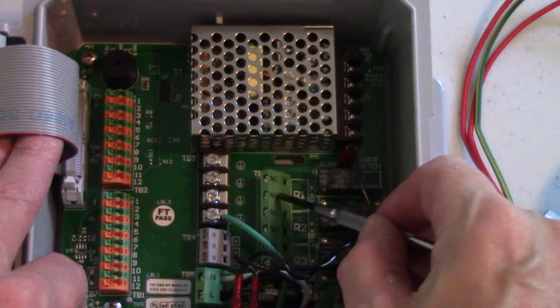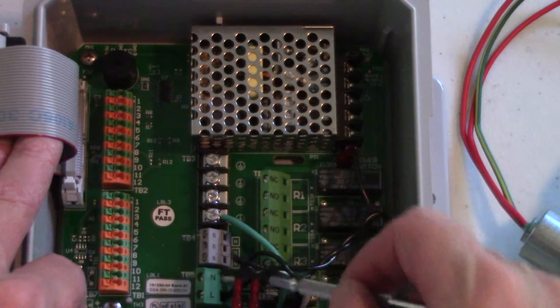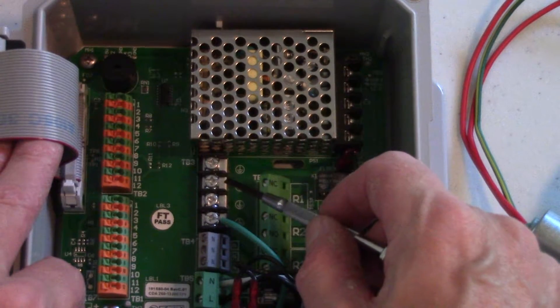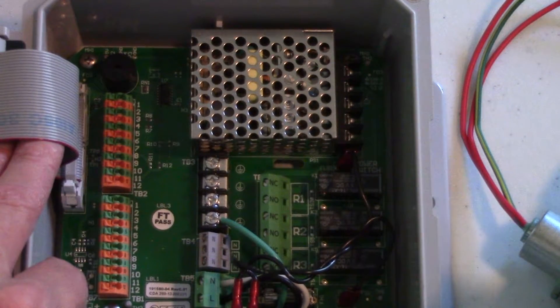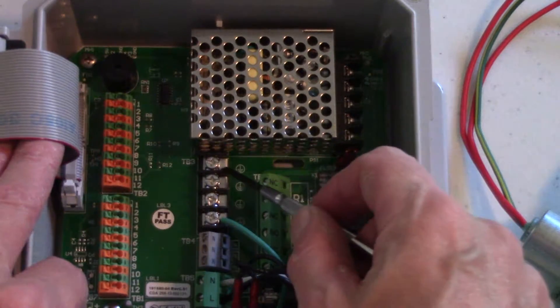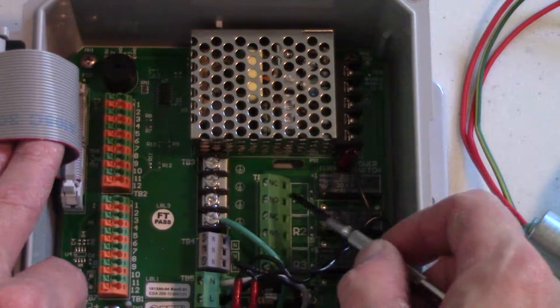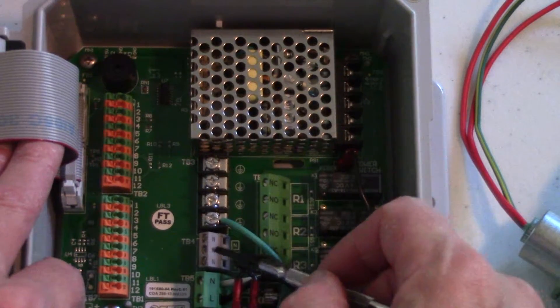Here is R1 and the normally open. Here is TB4 and here is TB3 for the ground. Now remember the solenoid valve has three wires. The ground we're going to wire up here and the other two wires to normally open on R1 and the other one on TB4.